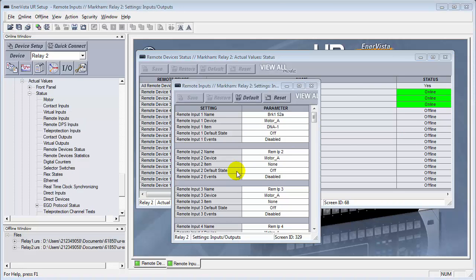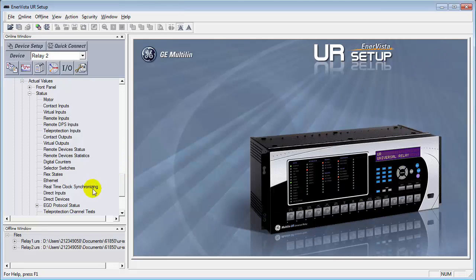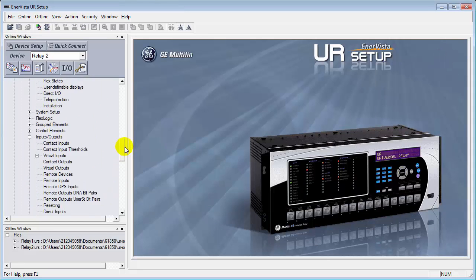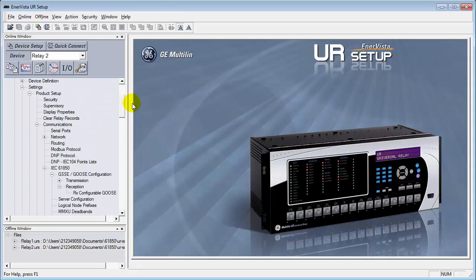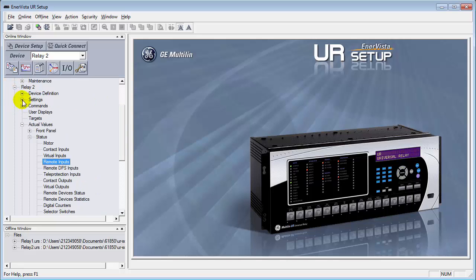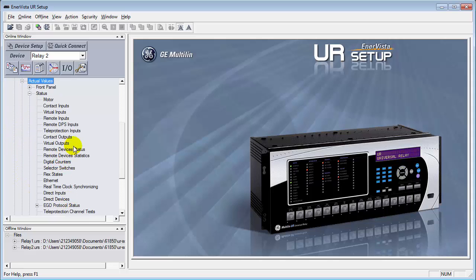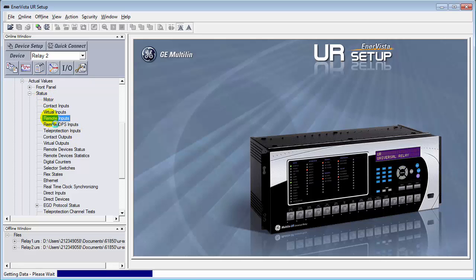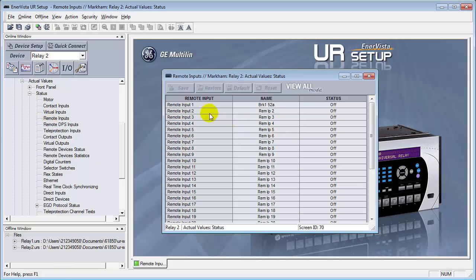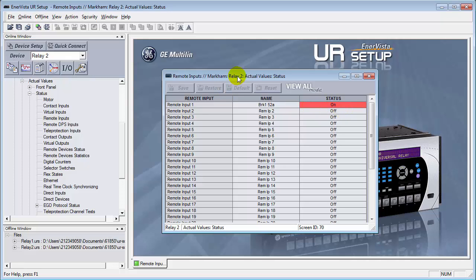Next, what we'll do is we'll confirm that the goose message is now being published across. Let's close these down. So what we're going to do is we're going to go on relay number two. So let me just minimize some of these settings here. We're going to go to relay number two. We're going to go down to actual values. And we're going to confirm that the goose message has been published and the subscriber is seeing the values. So under actual values, we're going to go to status and we're going to go to remote inputs. When we open remote inputs, we'll see the name of the goose message signal that we're interested in. Breaker 152A, Antoine, close the switch for me. So it was verified that, yes, it did change states. So the message is getting across to relay number two. This concludes the goose publication, or the subscriber side of the fixed goose.